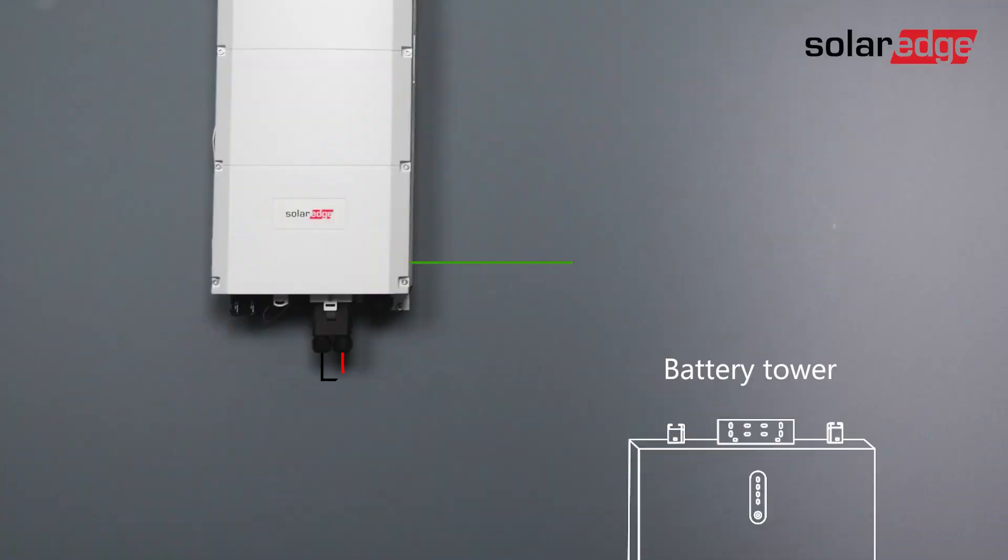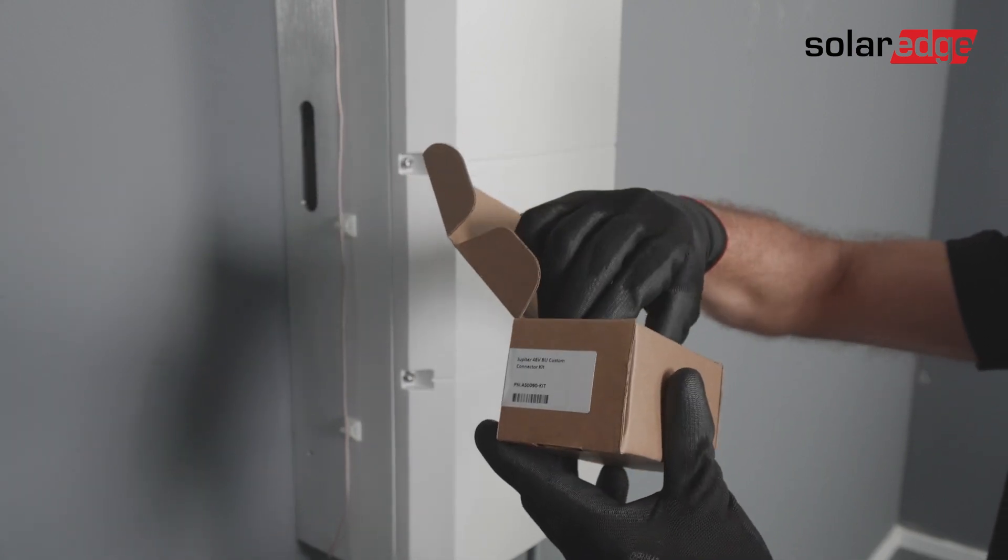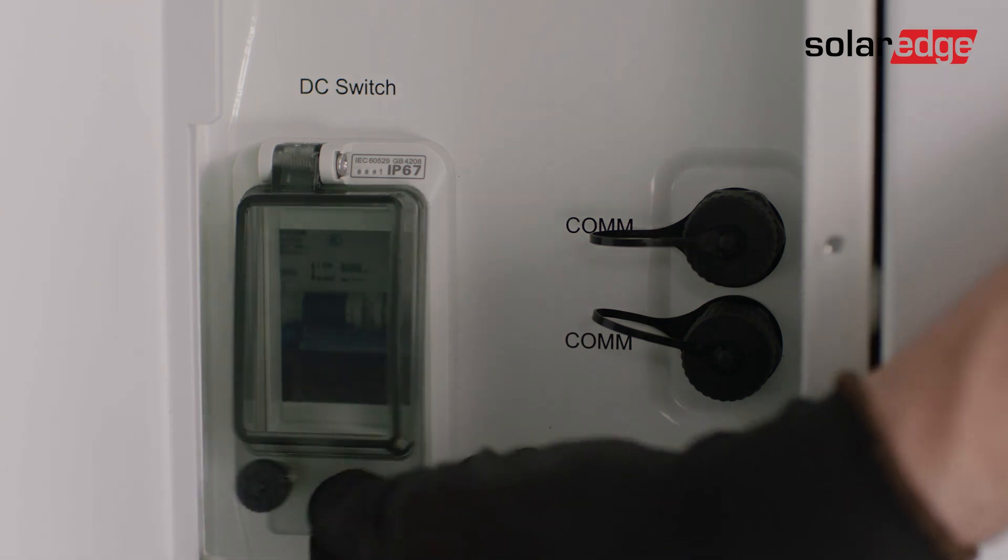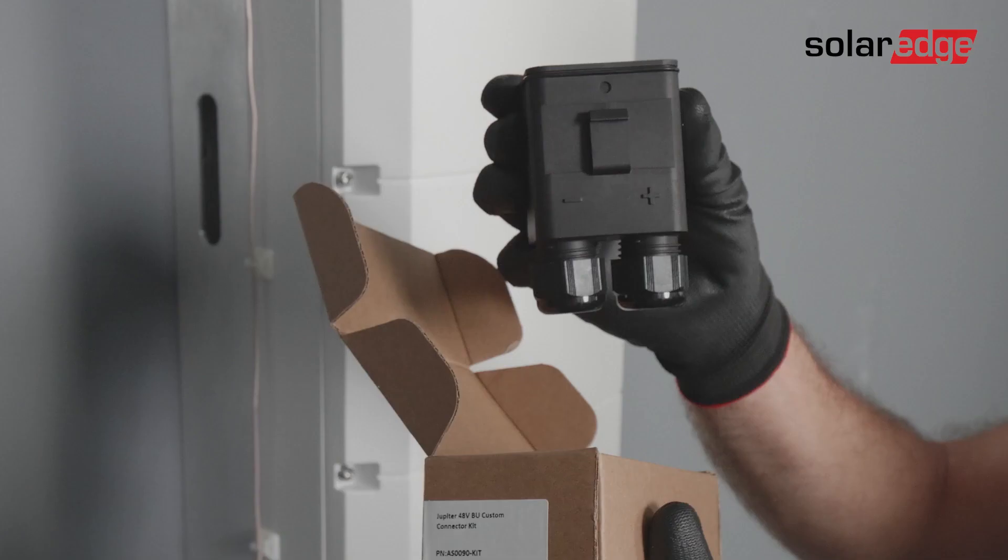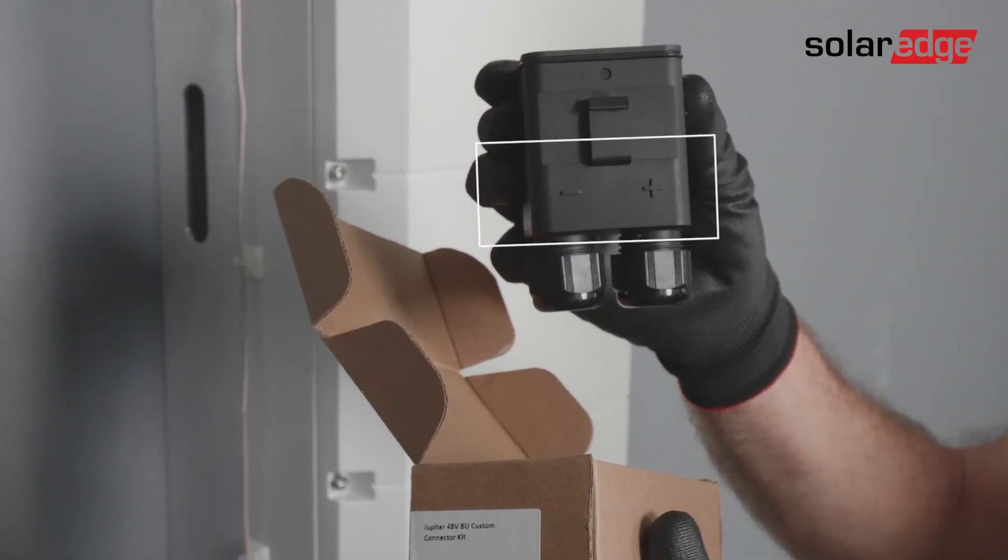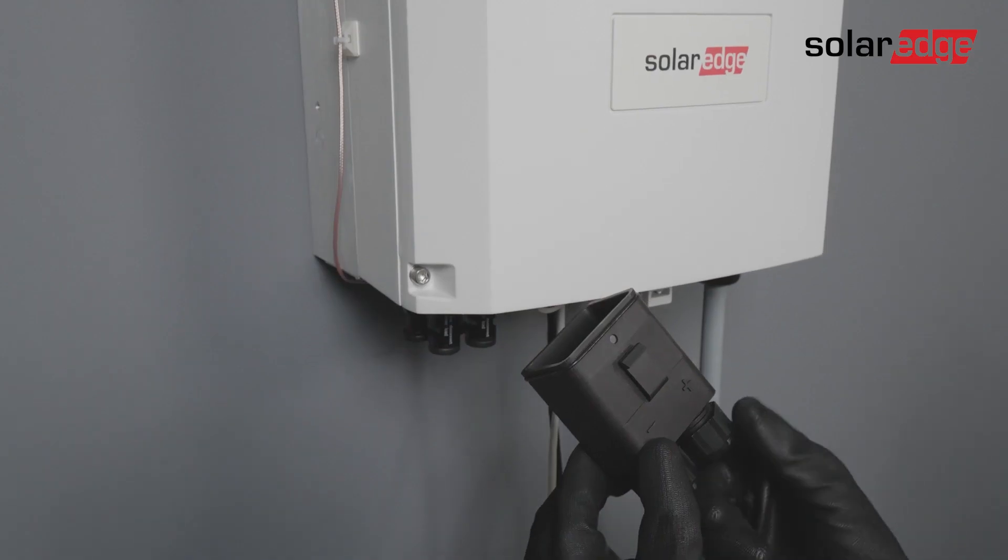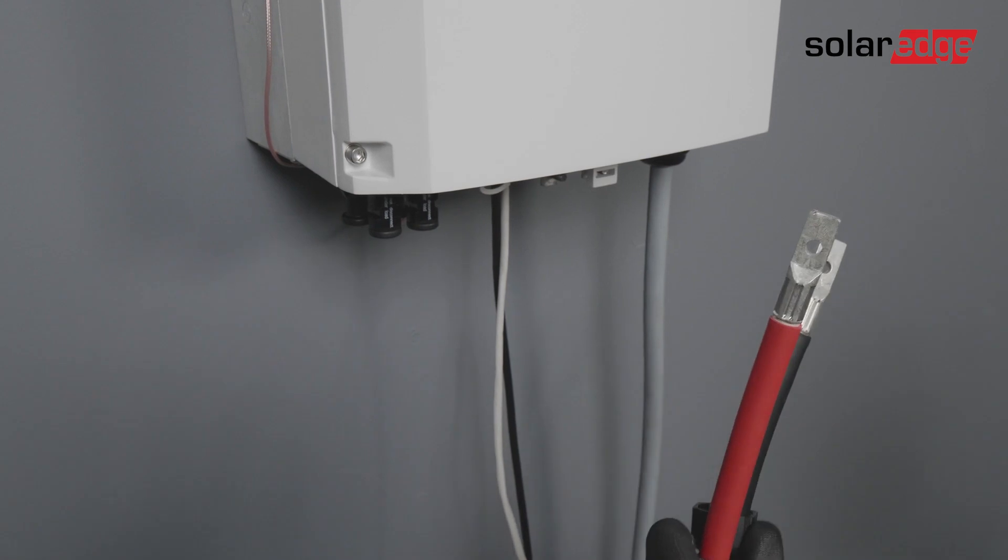Now, let's connect the ground and DC cables to the battery. Take the DC connection kit out of the box. Make sure that all battery module's circuit breakers are off before making any connection to the inverter. Please note the polarity as noted on the connection kit and that the snap is facing you. Open the cable gland nuts and pass the battery DC cables through the glands.